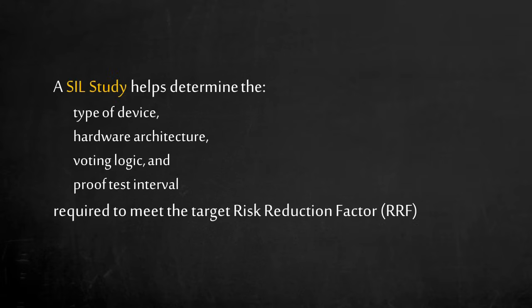A SIL study helps make these decisions. The type of device, such as the type of sensors, logic solver, valves, hardware architecture, the level of redundancy, if any, voting logic, how an action is initiated based on conflicting signals, and the proof test interval, how and when each component within the safety function should be tested. All of these are required to meet the target risk reduction factor, or in other words, the safety integrity level of a safety instrumented function.